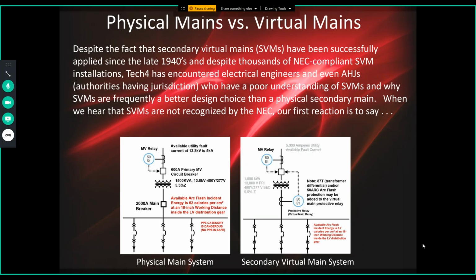So the bottom line, the key point I want to make, is not only is a secondary virtual main a great technical solution in terms of reducing system complexity, you completely eliminate that 2000 amp main breaker and main breaker section. But you get a safer system. You can see dramatically lower arc flash incident energy in the secondary switchgear, and you can deliver the system for just about the same amount of money, or even slightly less money, with a secondary virtual main. The cost of the CTs and the protective relay is much, much less, a fraction of the cost of the 2000 amp secondary main breaker. Any questions?